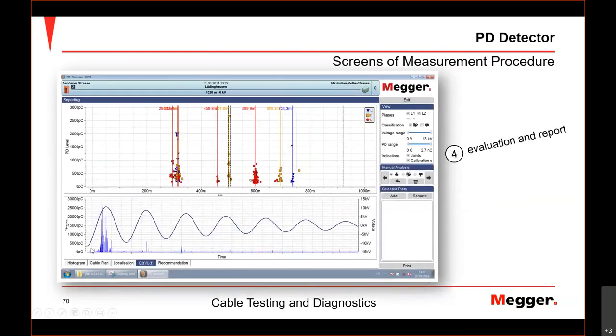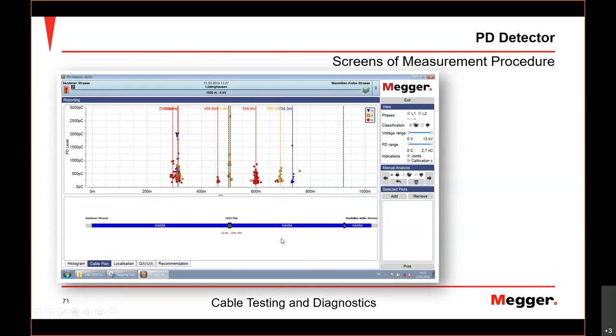If we look at a picture like this, our noise level here is very small. The blue line at the bottom, we have a scale now that's much too high. But we would see that higher, this just the noise ground level. And if you had periodically appearing pulses, actually we do have some here. See, there's one here, there's one here, there's one here. They're very periodic. So there is a noise source somewhere, and it causes disturbance. We have to watch out that we don't confuse them with partial discharge. But we see right away there is a periodic noise going on, some rectifier. We can take that into consideration, but it's not that important if it doesn't overlay all of our measurements, just knowing that it's there.